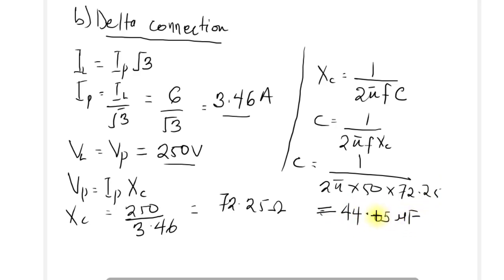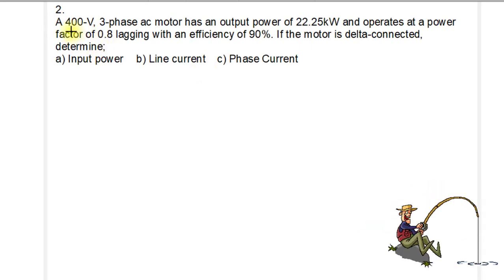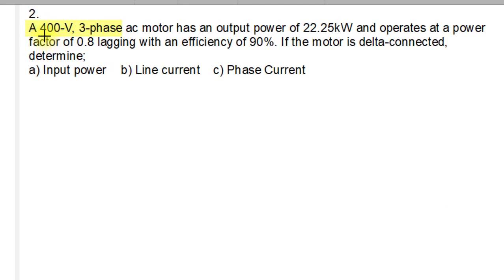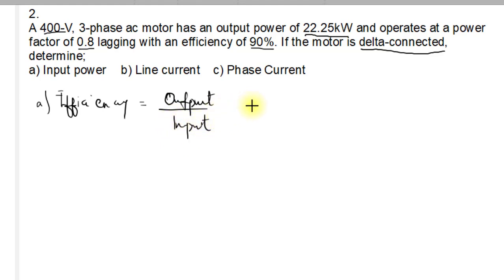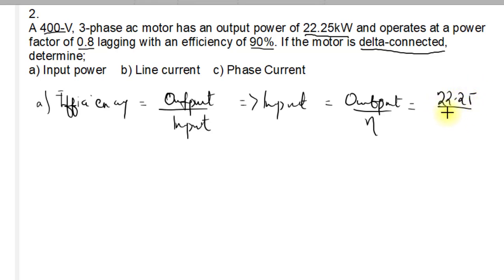For question 2: a 400 volt three-phase AC motor has an output power of 22.25 kilowatts, operates at a power factor of 0.8 lagging, with an efficiency of 90%, and is delta connected. To find the input power, efficiency equals output power divided by input power, so input power equals 22.25 kW / 0.9 = 24.72 kilowatts.